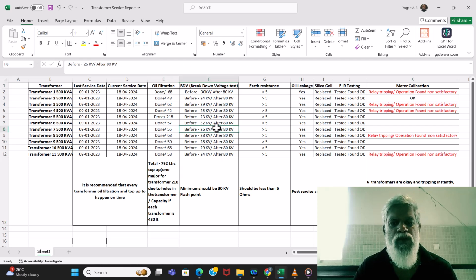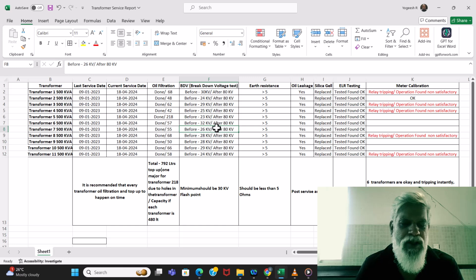Coming to the breakdown voltage test, it's a simple method: we take this particular oil, put it into the testing equipment, and flush it with electricity in kilovolts. At what point the flash occurs determines if our breakdown voltage test is okay or not. So before we service the transformers, this is the list that shows the readings.